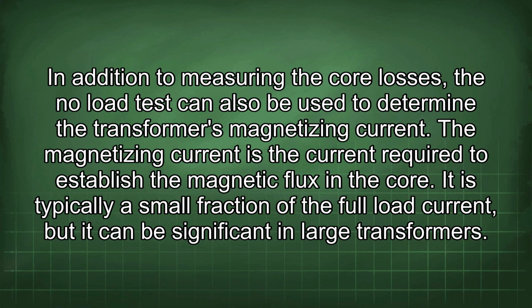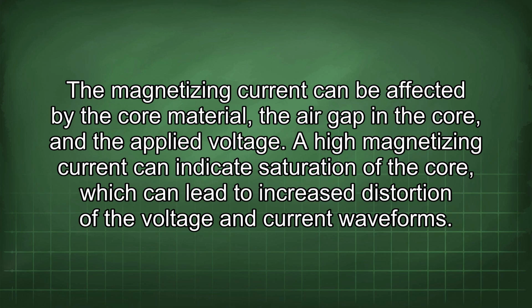In addition to measuring the core losses, the no-load test can also be used to determine the transformer's magnetizing current. The magnetizing current is the current required to establish the magnetic flux in the core. It is typically a small fraction of the full load current, but it can be significant in large transformers. The magnetizing current can be affected by the core material, the air gap in the core, and the applied voltage.